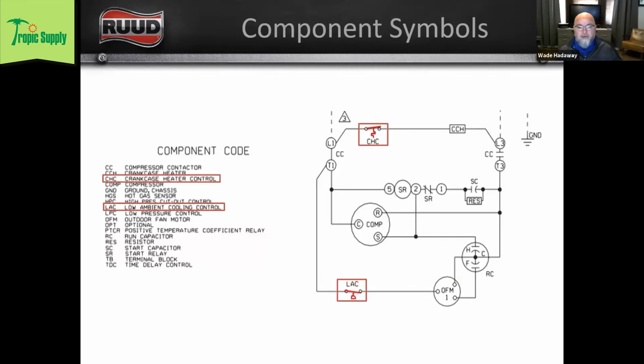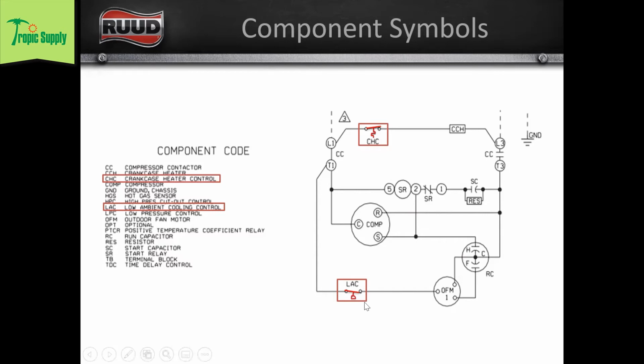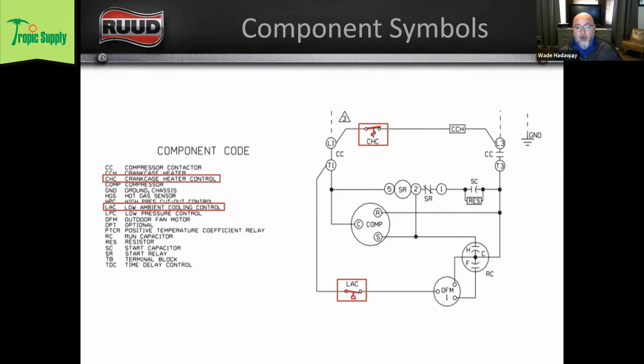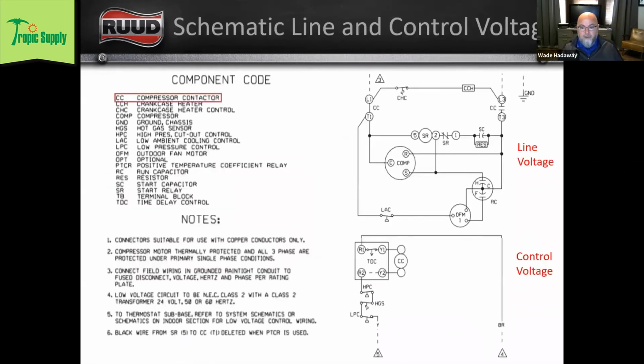Okay, you're talking about the symbol itself? The symbols are different because this low ambient control is based on pressure, not temperature. So it's not a temperature switch, it's a pressure switch. And the crankcase heater control is a temperature switch, and that's the difference between the two symbols. Whether it's open on rise or close on rise doesn't really matter. This squiggly line tells me temperature, and this half moon tells me pressure. What designates open on rise or closed on rise is how it's lined up with the contacts on the switch. I hope that answered the question.